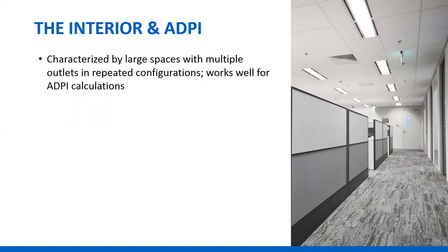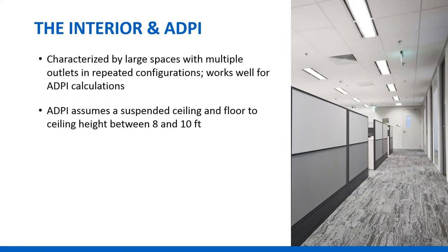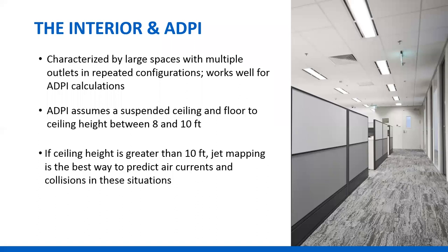Spaces with eight to ten foot ceilings with a suspended ceiling and diffusers located in the ceiling are ideal for an ADPI analysis. If the ceiling is outside of eight to ten feet, we have to do some kind of jet mapping because the ADPI calculations assume a certain ceiling height. Jet mapping is also required in places where we may have collisions with beams and soffits.